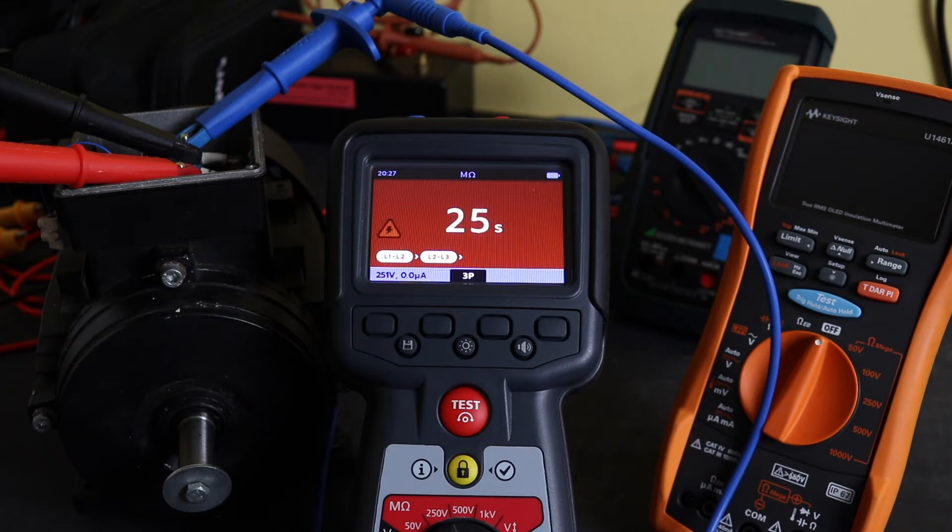So we're into the final 30 seconds of the test, and you can see how it operates. It does the first test of L1 to L2, flashing away the phase that's under test, then L2 to L3, and then finally L3 to L1. And you can see that despite the time function being set to 30 seconds, it still just does it as a one minute test. So there doesn't appear to be a way around that.